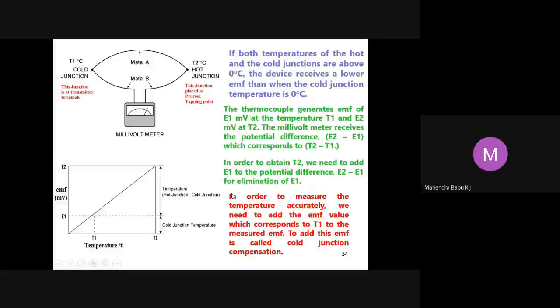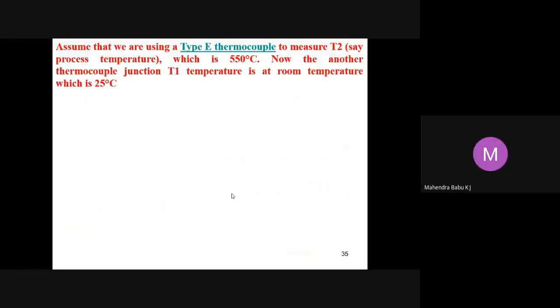Therefore, in order to measure the temperature accurately, we need to add the EMF value which corresponds to T1 to the measured EMF. Adding this EMF is called the cold junction compensation. To understand this more clearly, let us assume that we are using a type E thermocouple to measure T2, which is a process temperature. Let this process temperature be 550 degrees Celsius, and the other thermocouple junction T1 be at room temperature, which is 25 degrees Celsius. Here the process temperature is 550 degrees Celsius, and the reference or room temperature is 25 degrees Celsius.